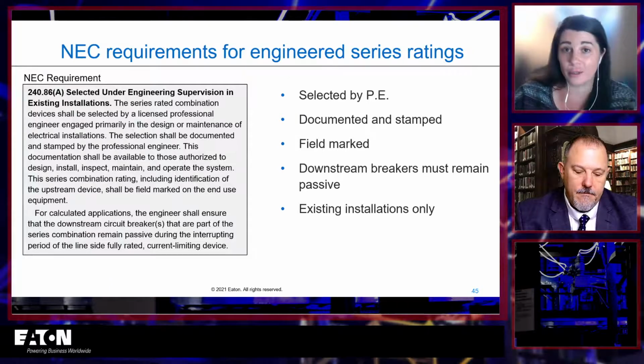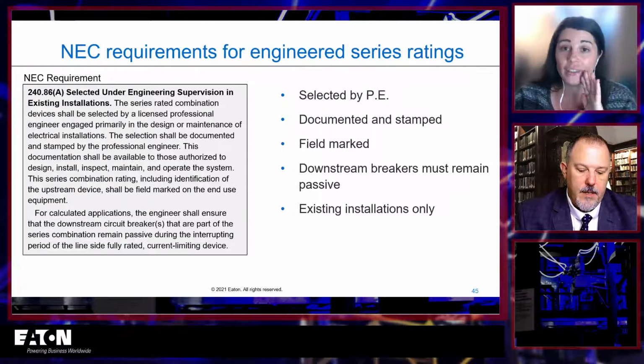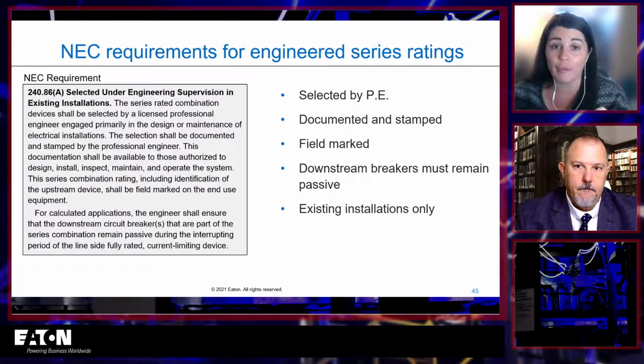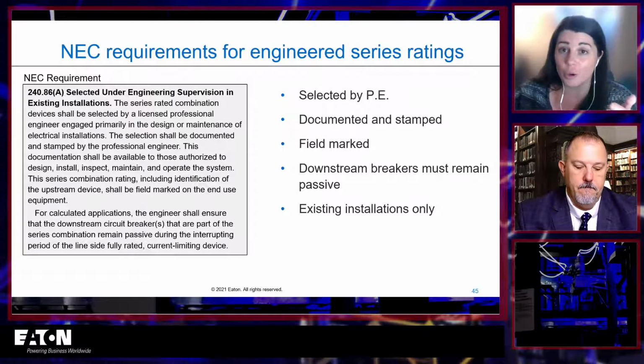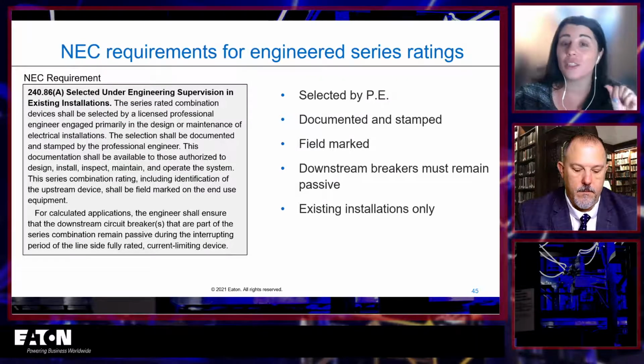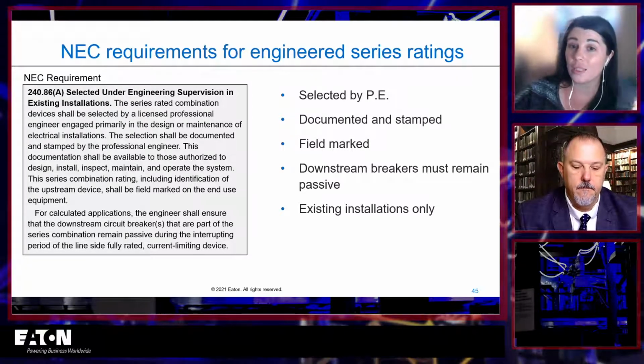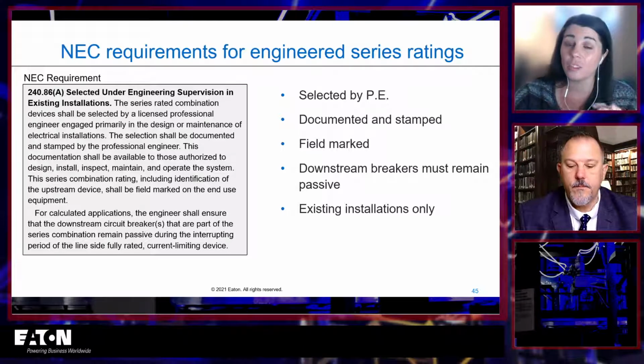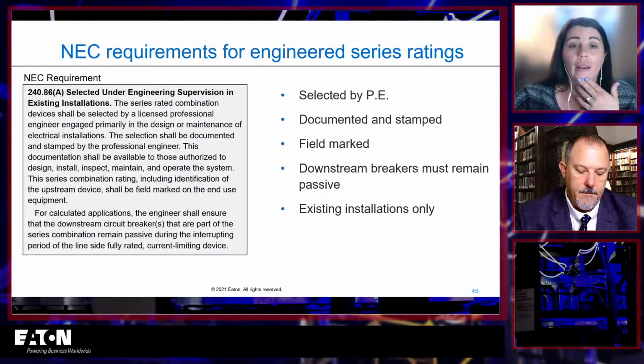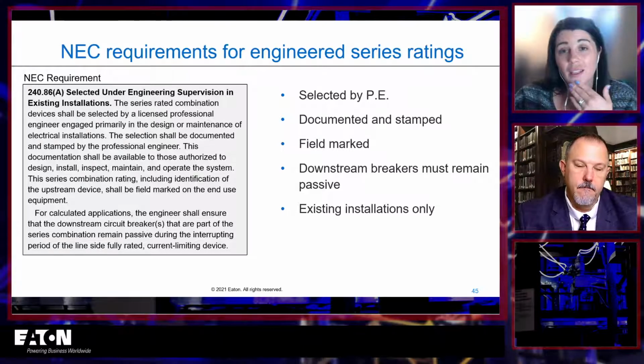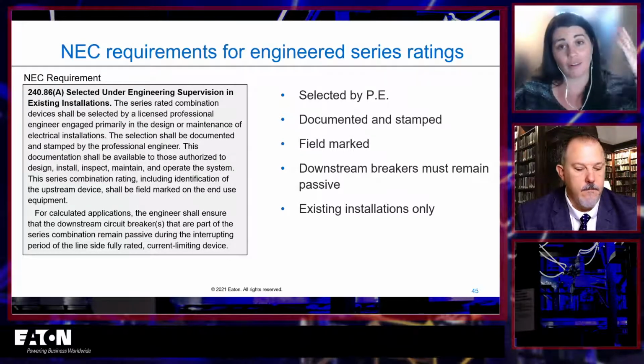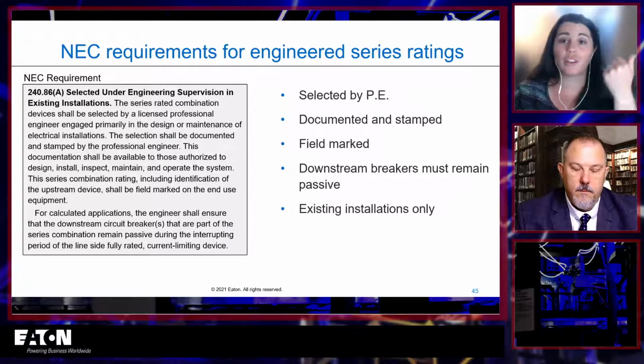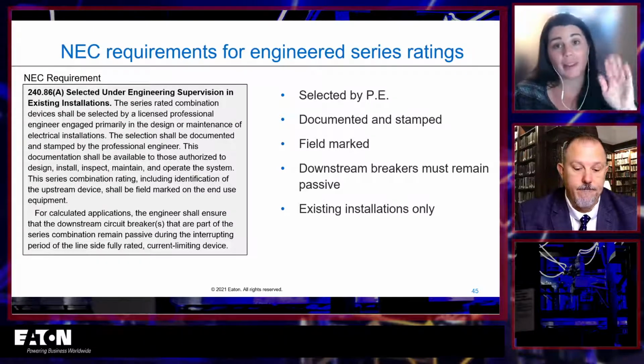So the idea that you would ever do it on purpose for new equipment is there are a lot of requirements. I'm only kind of touching on some of them here, but you've got an additional requirement to count up all your motor contributions. There's a lot that goes into the labeling in the field to make sure this all goes right. And there's just a lot of liability, and it's do you want to be in charge of that liability, or do you want the manufacturer listing on the panel to be in charge of it? I know what I'd pick.